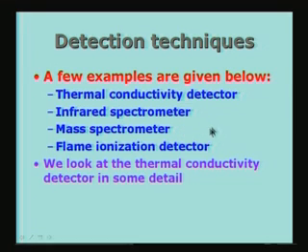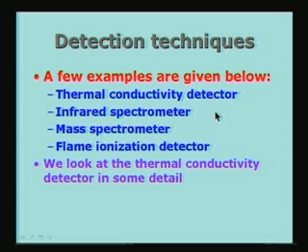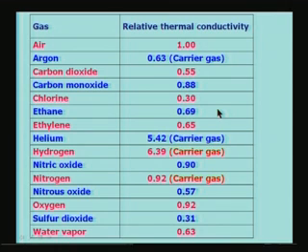So, we will look at the thermal conductivity detector in some detail, and that requires a little background on the process which may take place. If you look at gases, the different gases have different thermal conductivities. This is a very important observation. So, some gases have higher thermal conductivity than others, and let us look at some of the typical gases which we meet with in practice.